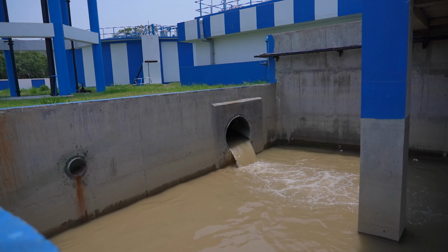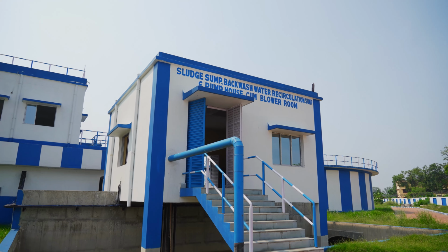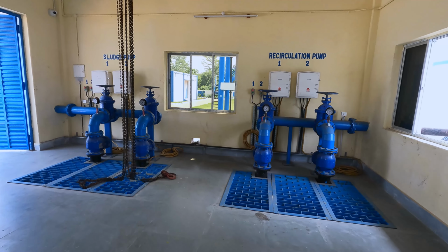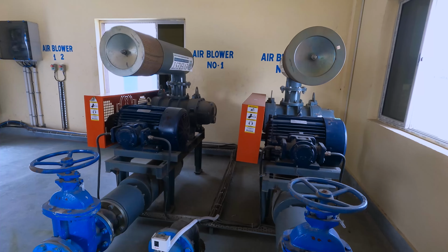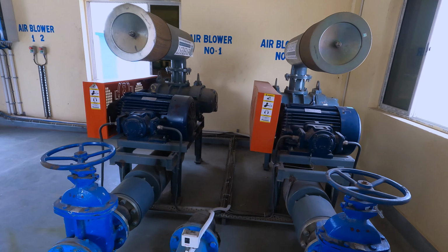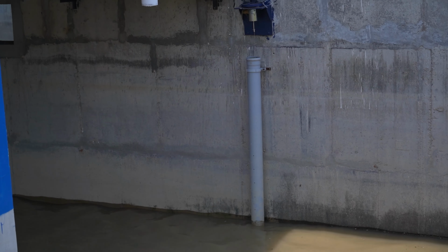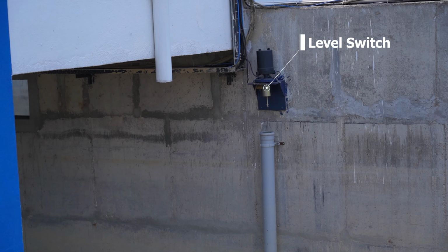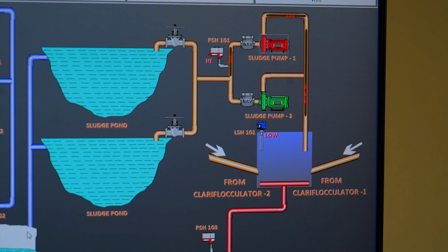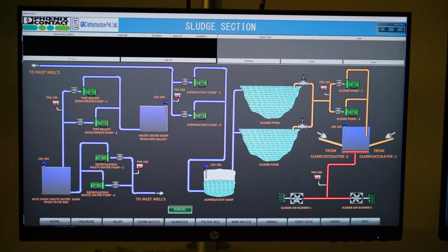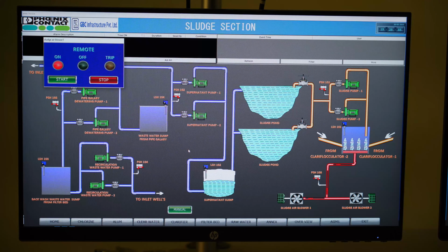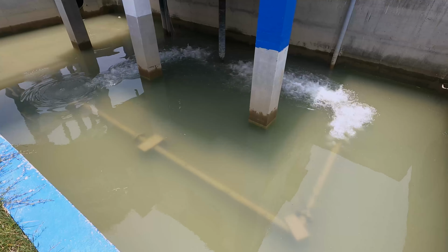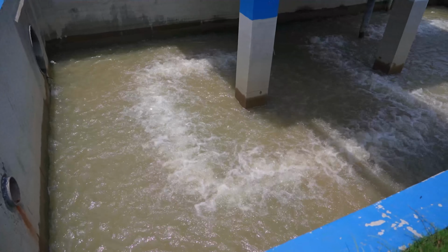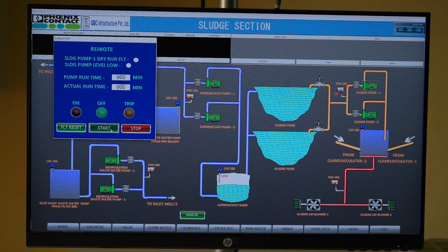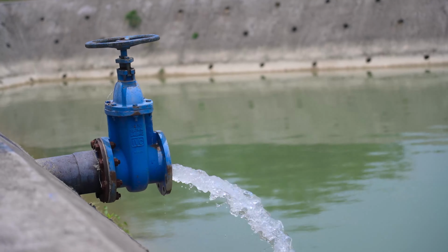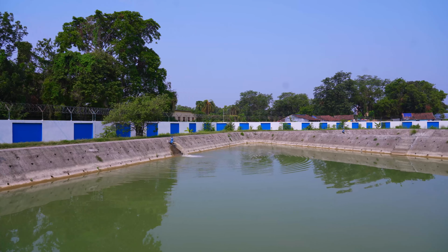In this house, the sludge collection sump and the backwash wastewater collection sump are placed side by side. The sludge pump, wastewater recirculation pump and sludge air blower are placed inside the house. The level of water in the sludge tank is monitored by a level switch, and whenever necessary it is recirculated to the inlet wells by choice. Here, first the air blower starts to purge the mud so that it doesn't settle down. The mixed sludge water is then pushed to the sludge lagoon by starting the sludge pump again with a click of a button. There are 2 sludge lagoons inside the campus.